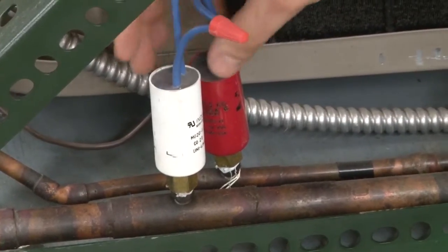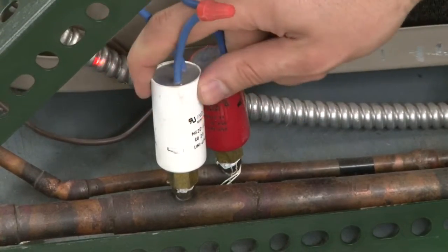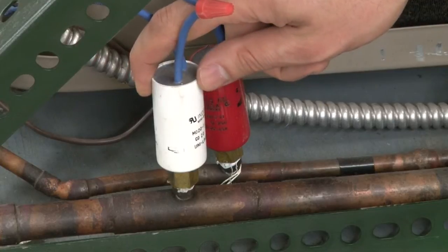So ideally what those would do, if your low side pressure switch opens up, you don't have enough refrigerant pressure, probably low on charge or another problem that would actually cause it to show low pressure.